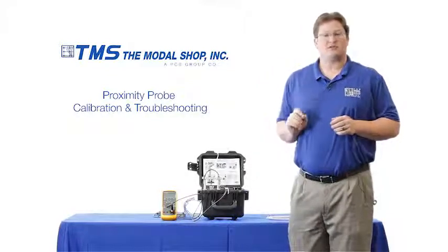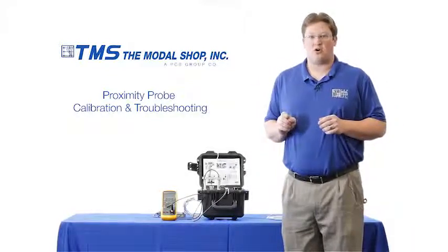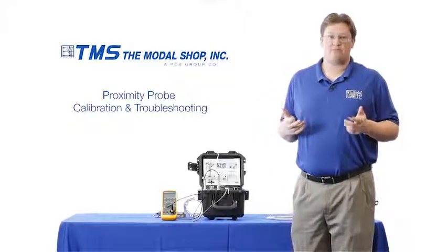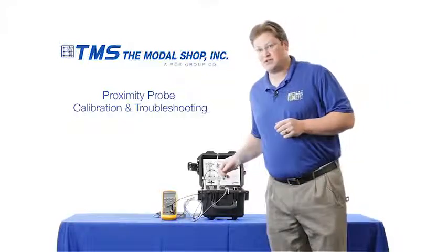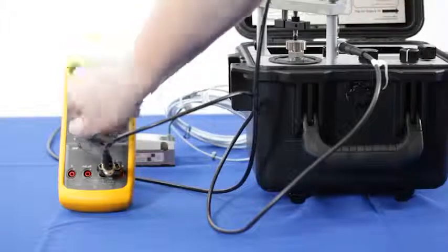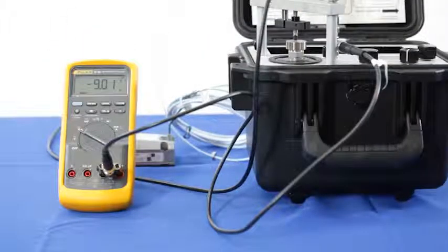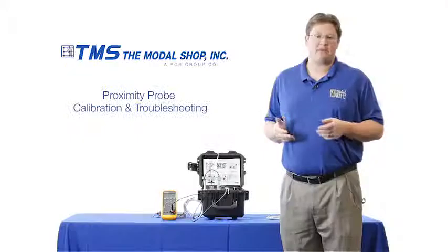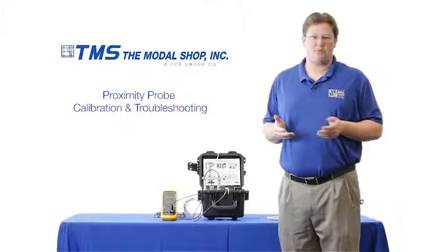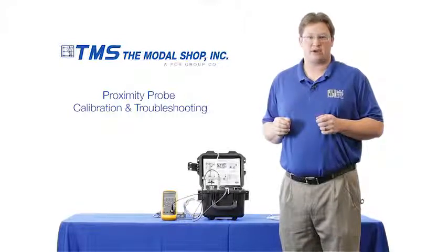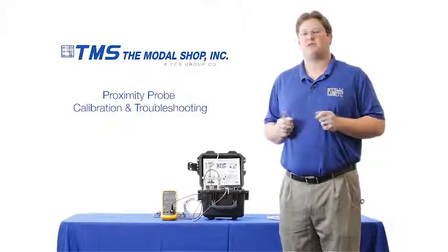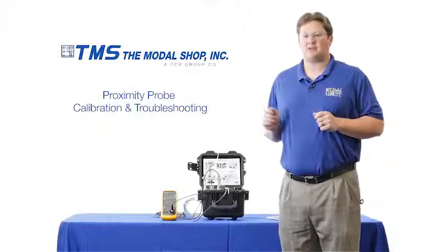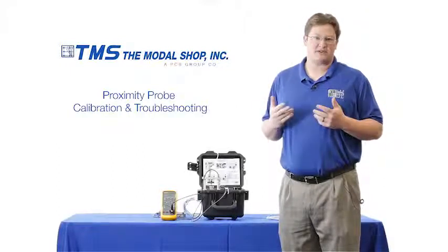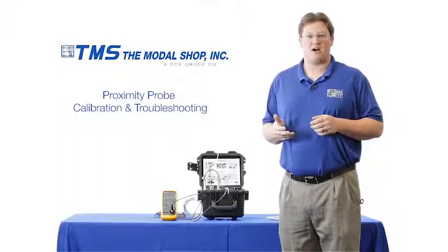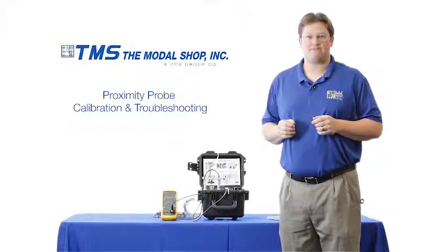The first thing I want to do when calibrating a proximity probe or installing a proximity probe is make sure my gap voltage is correct. And you'll see when I turn on the voltmeter that my gap voltage is at -9 volts. That means the tip of my proximity probe is 50 mils from the target. The proximity probe is linear from 10 mils to 90 mils, so being 50 mils from the target at the start ensures I'm in the center of my dynamic range.